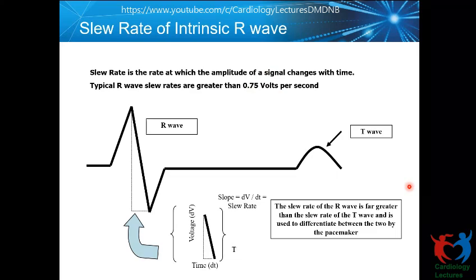And then you need to pay attention particularly, sometimes when you're implanting, most of the time you get a good R wave. Sometimes, because of some pathological reasons, you get a smaller R wave no matter how much you explore. So let's say you get only 3 to 4 millivolts R wave. Note the slew rate. The slew rate should be reasonably good at that point of time. So that's the rate of change of voltage in the R wave.